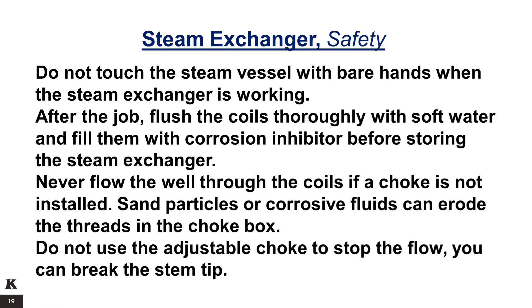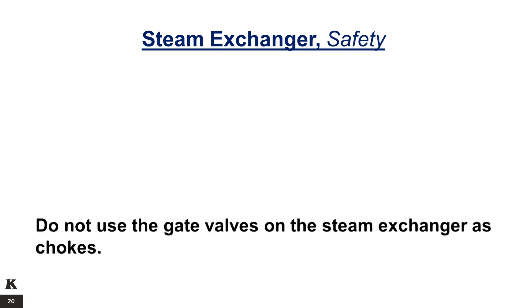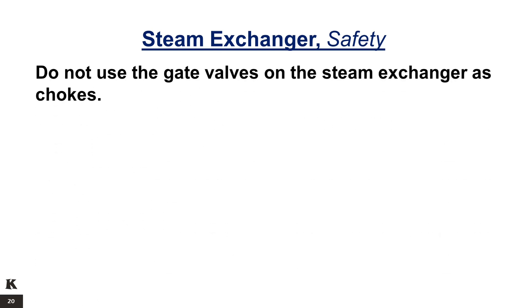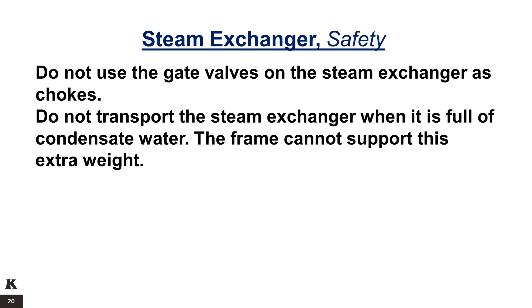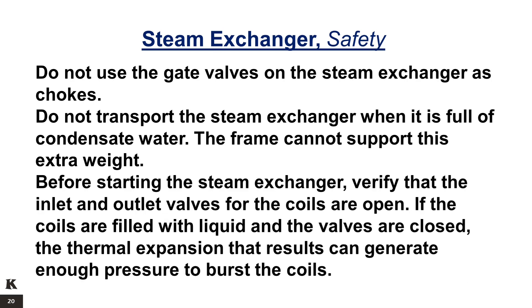Steam exchanger — Safety. Do not use the gate valves on the steam exchanger as chokes, as you can break the stem tip. Do not transport the steam exchanger when it is full of condensate water — the frame cannot support this extra weight. Before starting the steam exchanger, verify that the inlet and outlet valves for the coils are open. If the coils are filled with liquid and the valves are closed, the thermal expansion that results can generate enough pressure to burst the coils.